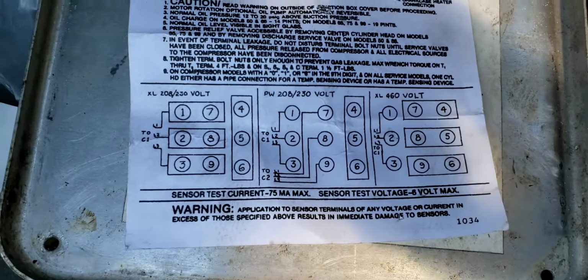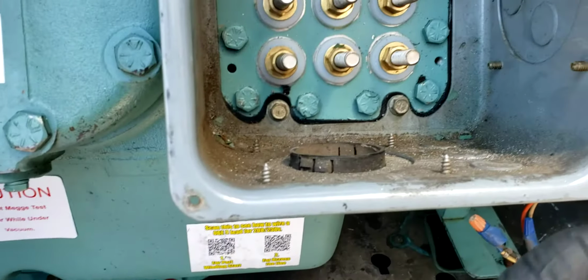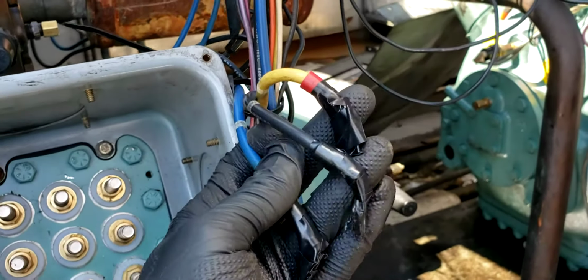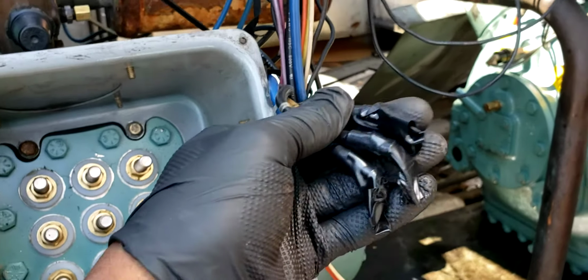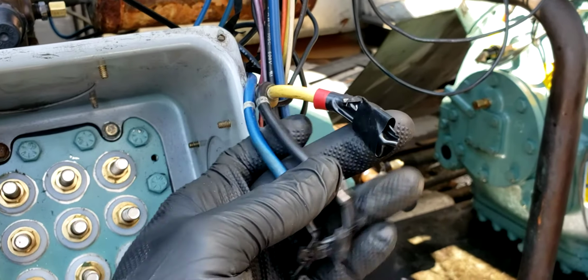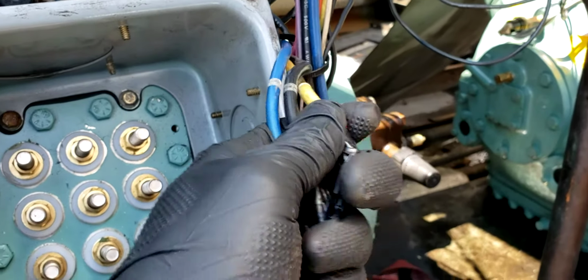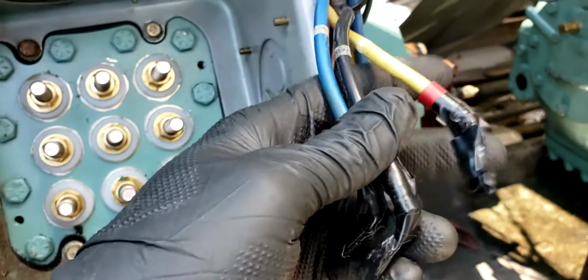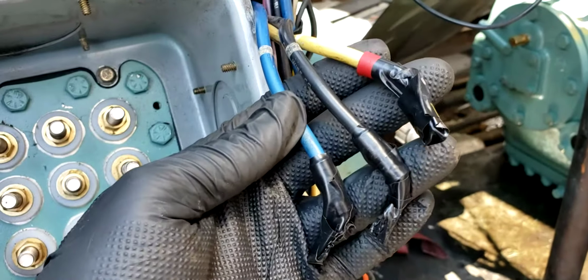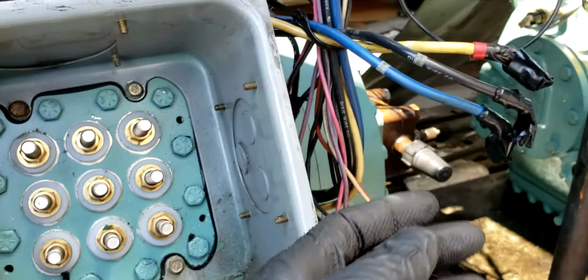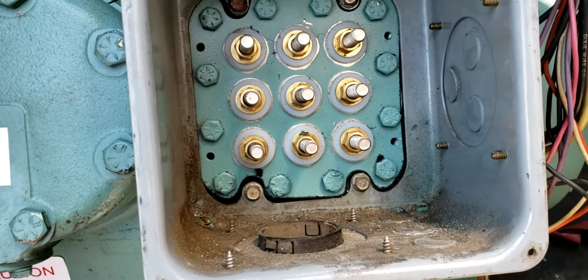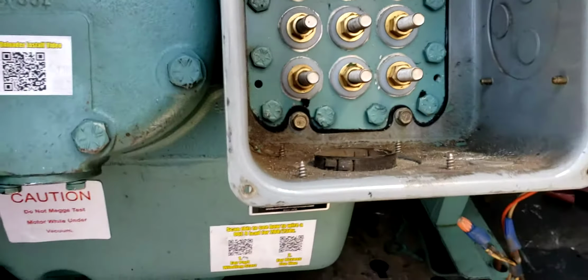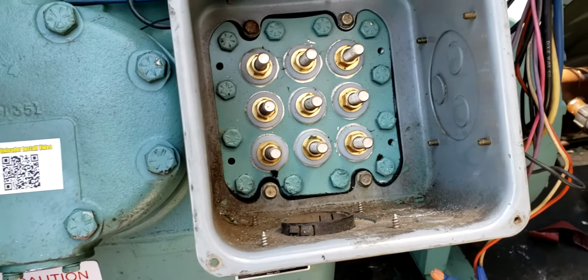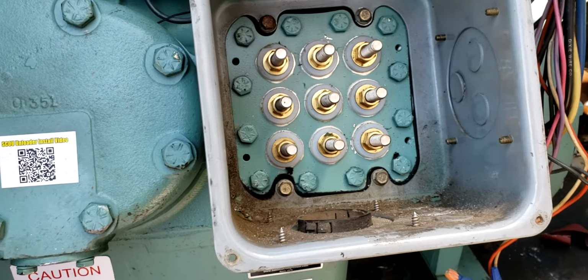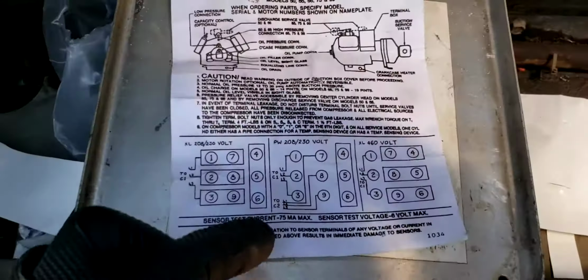And then with part winding start, as opposed to having 3 power wires only if you're doing across the line, if you have a part winding setup, it would be 6 wires coming here. You'd have 6 wires and 2 contactors controlling this compressor for part winding startup. Now, those contactors wouldn't pull in exactly at the same time. They won't get energized exactly at the same time.